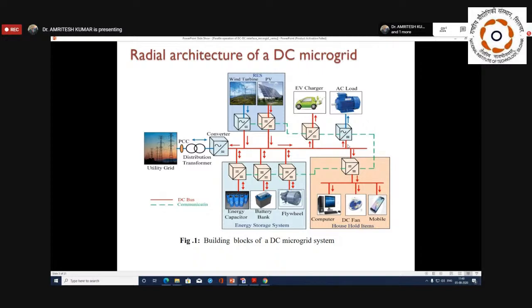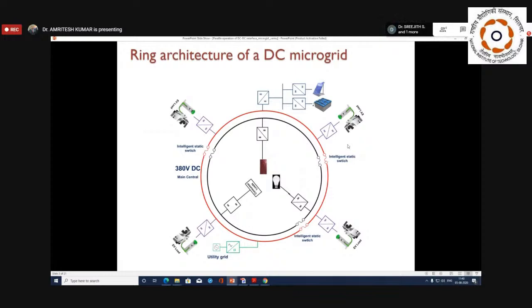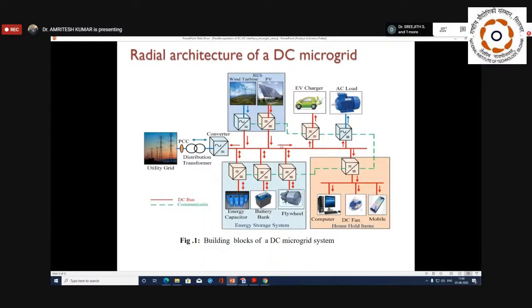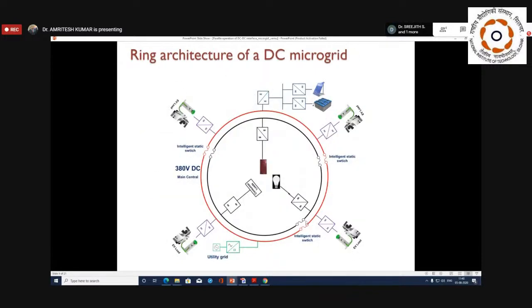Instead of a radial system, we can also have a ring architecture of a DC microgrid. In a radial line, if there is a fault at one location in the DC grid, the whole unit may be disturbed. But with a ring main system like this, if any fault occurs, we may isolate it using intelligent static switches, and the rest of the loads can be catered easily. This is another architecture that people thought of for a DC microgrid, the ring main architecture.